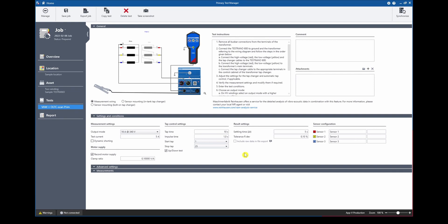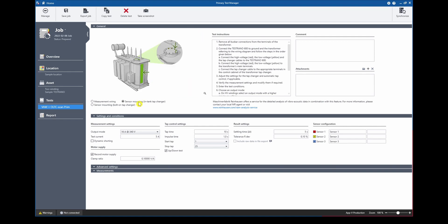Inside the Vibroacoustic measurement test we can see on top the connection diagram which shows the Testrano 600 that is connected to all transformer terminals and in addition we can also see the Vibroacoustic One module which is connected via the EtherCAT connection to the Testrano 600. In addition the connection diagram gives some recommendations where to place the sensors. In this case the green marked area on the right side of the transformer or the OLTC cover are recommended.